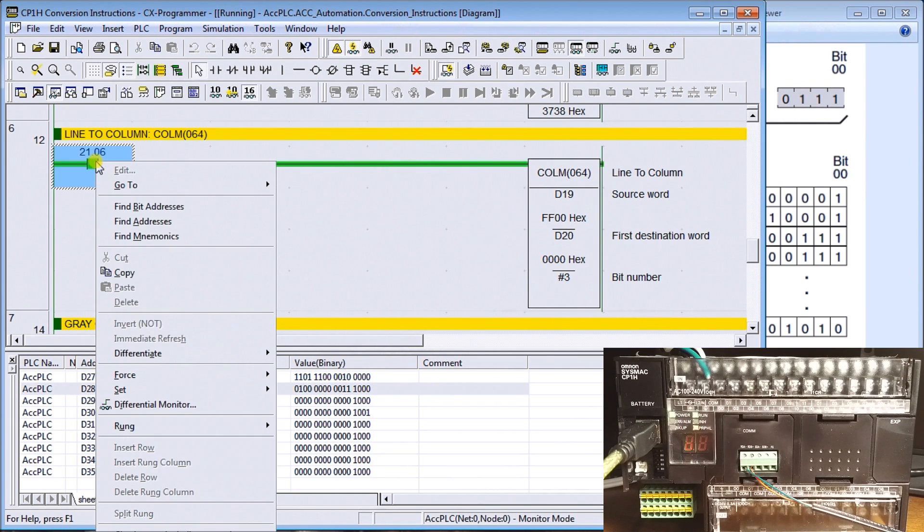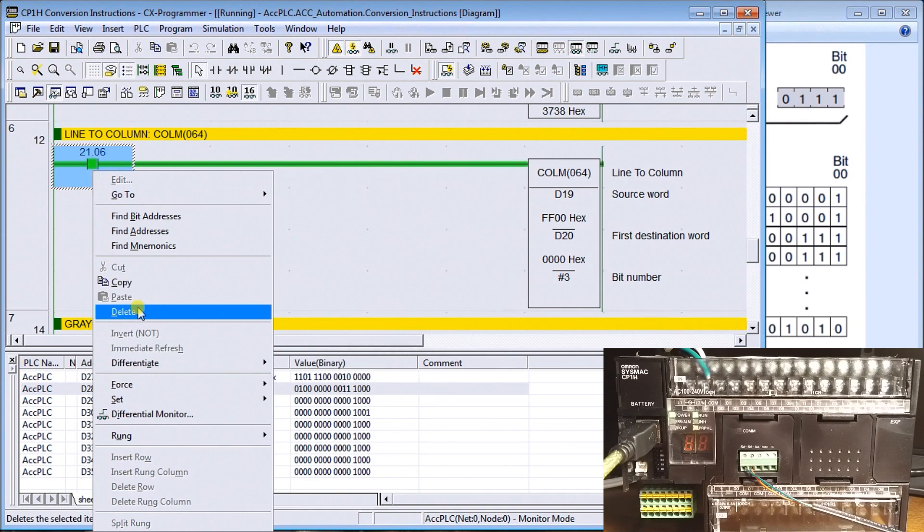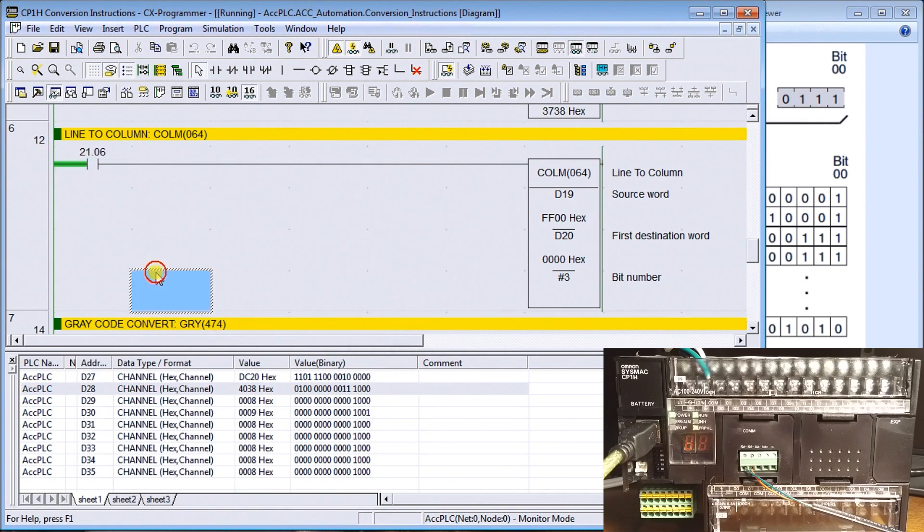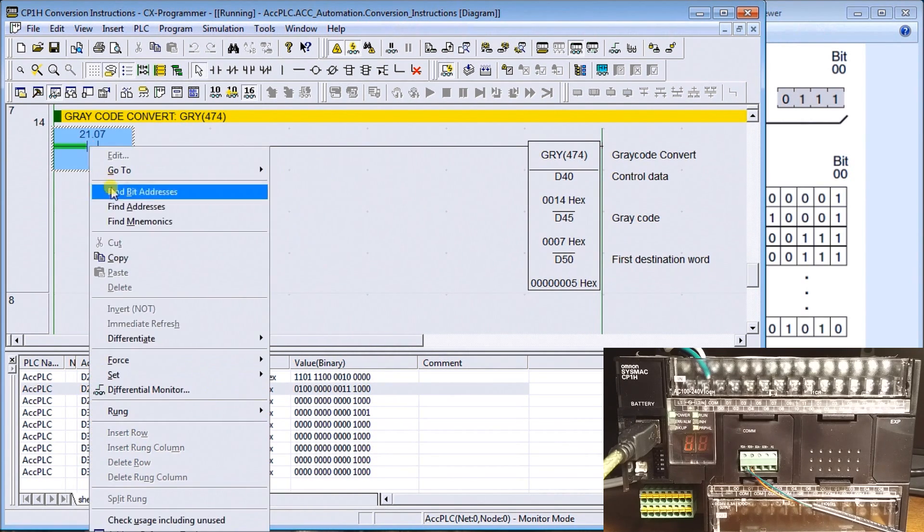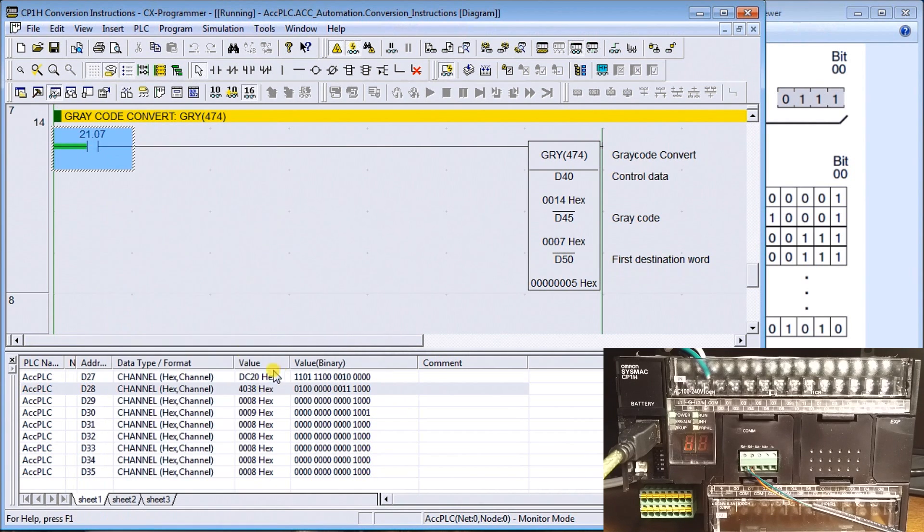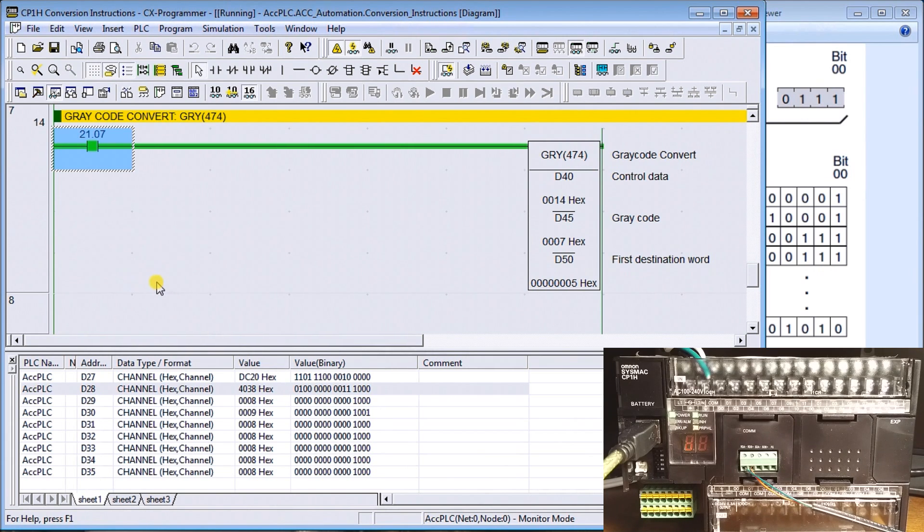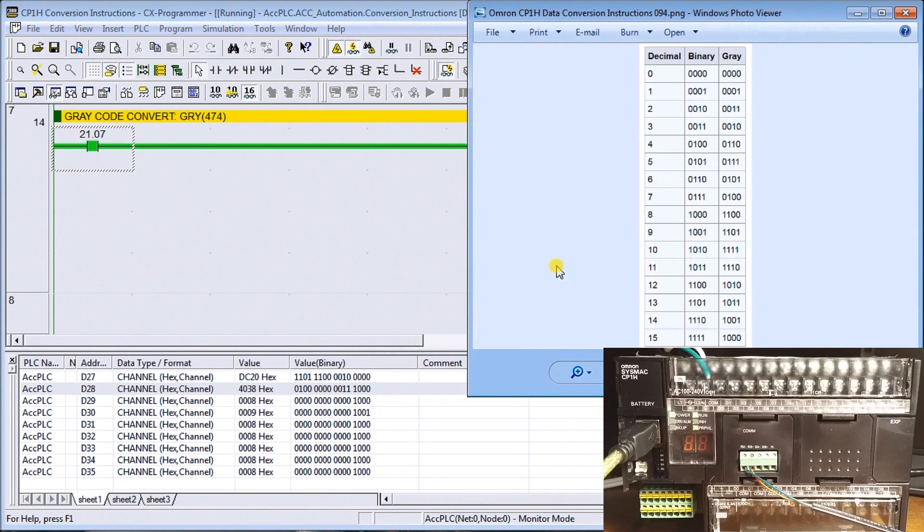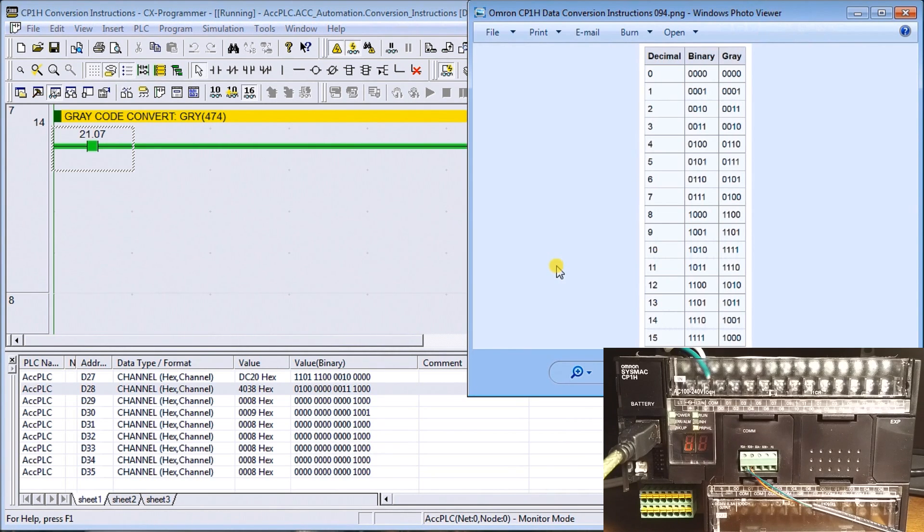The final instruction we'll look at today is gray code. Now gray code, what it will do is convert a gray code into either binary or BCD for us. The advantage of gray code is that every time a bit changes, only one bit changes. So if this is on a rotary encoder, as we turn that encoder, only one bit changes at a time. So we know exactly where we are when we power up this unit again.